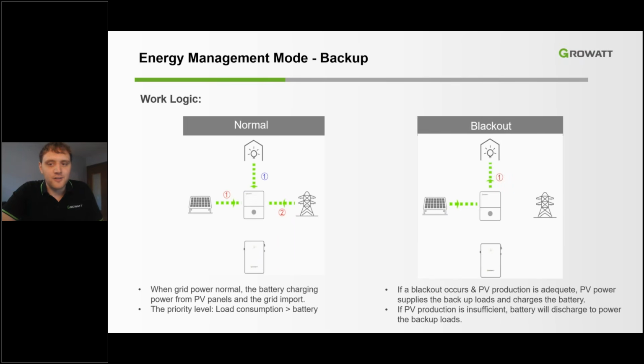So with these accessory products, whole home backup or critical load backup may be achieved through the EMS settings of the inverter. During backup mode, the PV production will supply power to the loads and charge the battery with excess energy. If PV production is not sufficient to handle all of the customer loads, the battery and PV production work in tandem to supply power to the customer's loads. This is critical in areas with frequent power outages or for customers who just want to be prepared for such an event. And again, the generator input allows for even more control of critical energy resources.